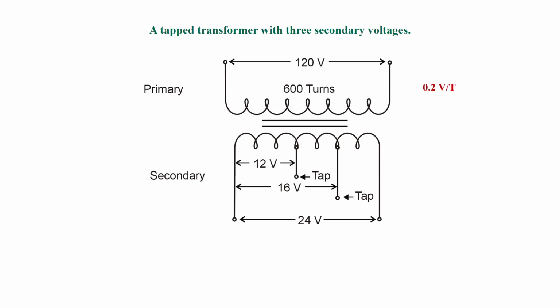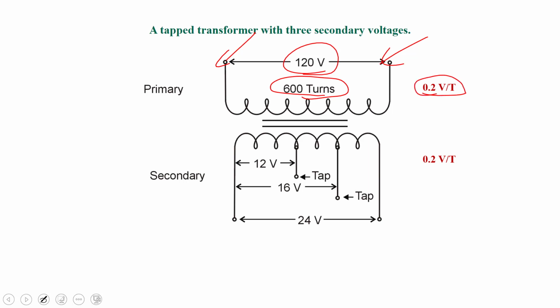So if you recall, when we apply voltage to the primary, right here, and in this case, rated voltage is 120 volts, we'll get the full 120 volts across all 600 turns. So we establish how many volts per turn based off the primary voltage that we apply and the number of turns on the primary. Now, whatever is established on the primary is going to be the same as it is on the secondary.